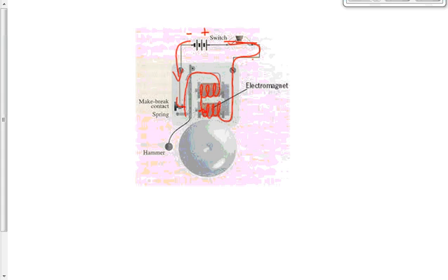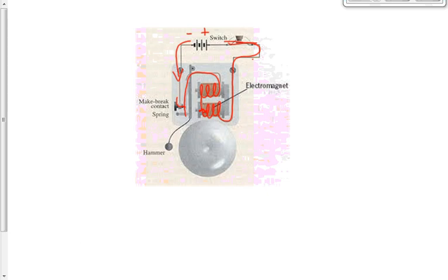What's the purpose of those guys? Yeah, go ahead, Bryce. Yeah. So this metal bar right here gets attracted to it. As it gets attracted to it, this hammer comes with it. What happens to the hammer as it gets pulled to the right? Hits the bell, right? What do you hear? Ding. Not the ding, ding, ding that you need for a fire alarm. You hear one ding.